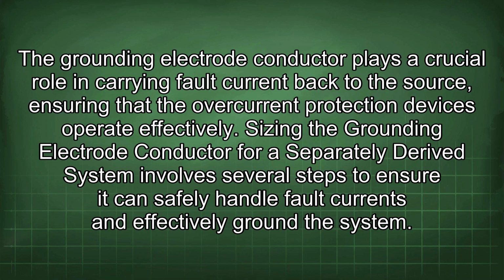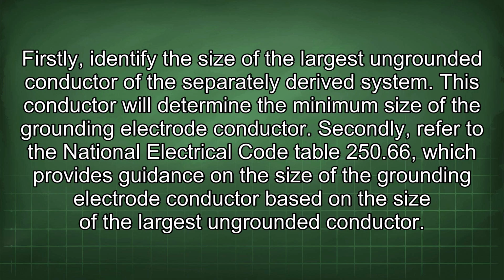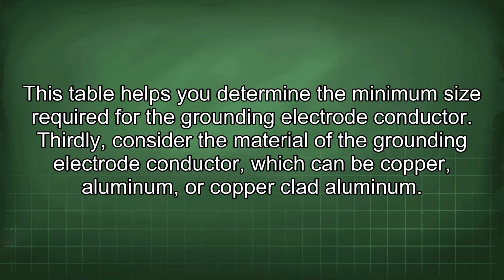protection devices operate effectively. Sizing the grounding electrode conductor for a separately derived system involves several steps to ensure it can safely handle fault currents and effectively ground the system. Firstly, identify the size of the largest ungrounded conductor of the separately derived system. This conductor will determine the minimum size of the grounding electrode conductor. Secondly, refer to the National Electrical Code Table 250.66, which provides guidance on the size of the grounding electrode conductor based on the size of the largest ungrounded conductor. This table helps you determine the minimum size required for the grounding electrode conductor.